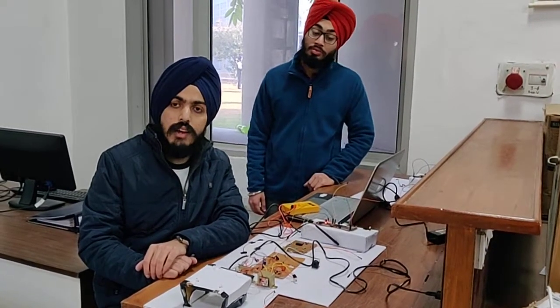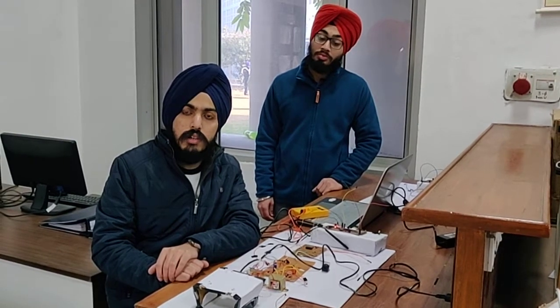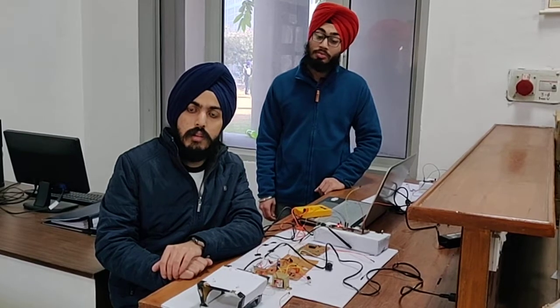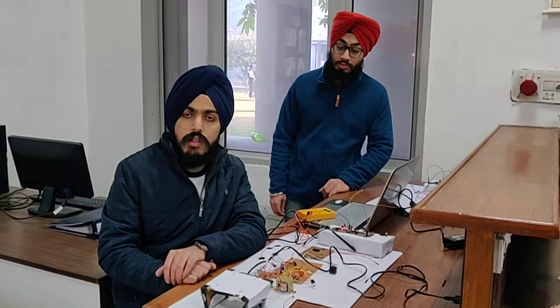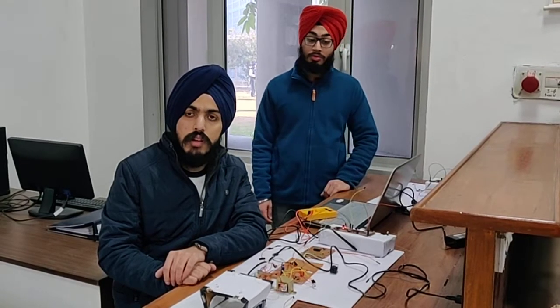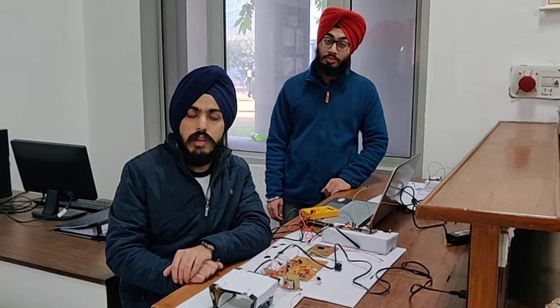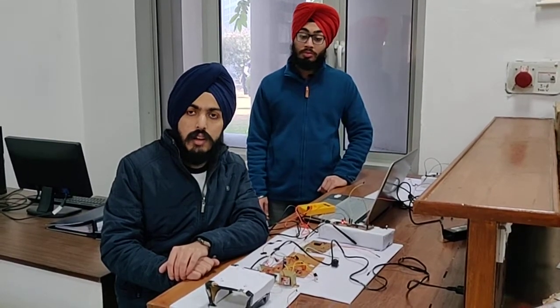Now the relay is like a guard. It continuously monitors the current and voltage parameters and other parameters in a circuit and sees whether there is any abnormal condition or not. If there exists an abnormal condition, it will immediately send a trip signal to the circuit breaker, and the circuit breaker is a switch that will isolate the faulty part. This is power system protection at a glance.